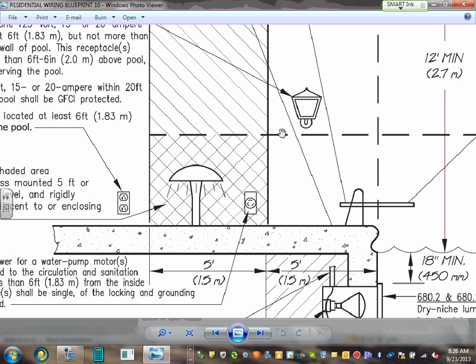Hydromassage bathtub, same thing, GFCI protected. 120 volt single phase receptacles located within 6 feet, measured horizontally from the inside wall of the hydromassage bath, must be GFCI. Anything within 6 feet of a hydromassage bathtub has to be GFCI receptacles. But I believe you cannot put them within 6 feet of that. Okay, same thing, bonding with number 8. You have to bond the plumbing piping system to the frame of the pump of the hydromassage bathtub with number 8 solid copper.